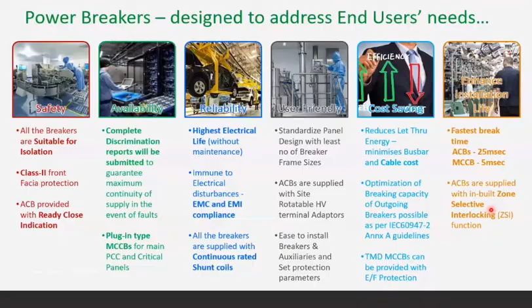Then our ACBs are supplied with built-in ZSI. In all the Schneider ACBs, the NW range or be it MTZ now, we have a built-in ZSI feature. Zone selective interlocking is a very good feature. If there is a fault present between any two breakers, they do not wait for the set time or the set threshold. These two breakers talk to each other, and the breaker nearest to the fault trips automatically using the ZSI. So let's see, after seeing this, what the future is and how the future is here with Schneider Electric.